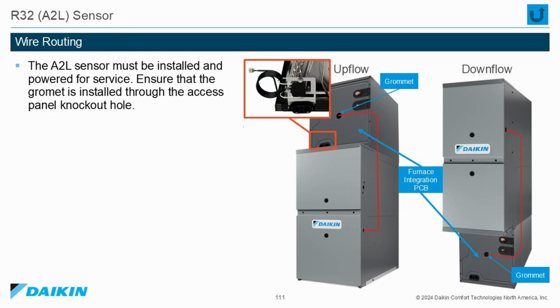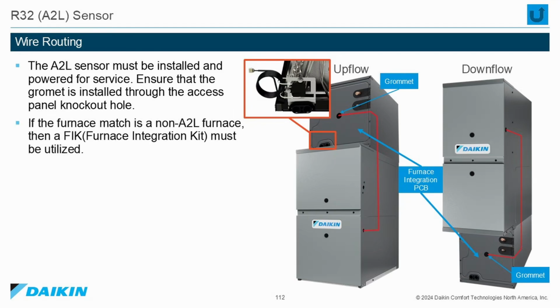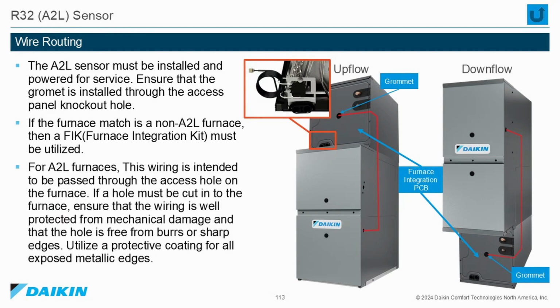Wire routing. The A2L sensor must be installed and powered for service. Ensure that the grommet is installed through the access panel knockout hole. If the furnace match is a non-A2L furnace, then a FIK, furnace integration kit, must be used. For A2L furnaces, this wiring is intended to be passed through the access hole on the furnace. If a hole must be cut in the furnace, ensure that the wiring is well protected from mechanical damage and that the hole is free from burrs or sharp edges. Use a protective coating for all exposed metal edges.